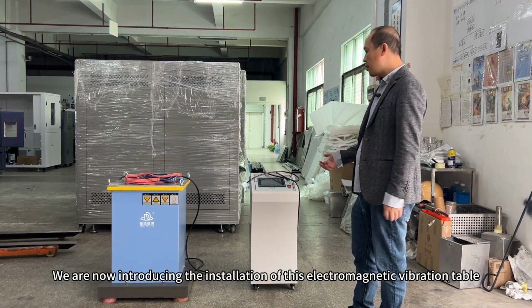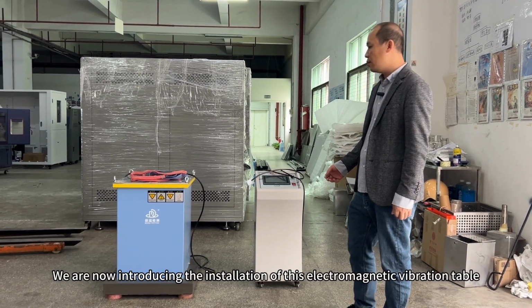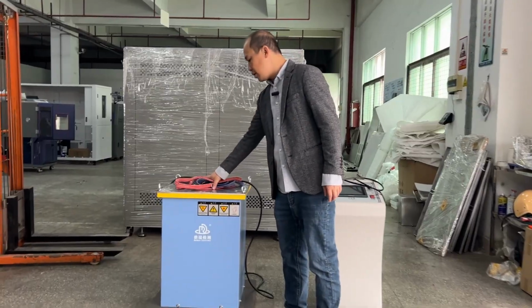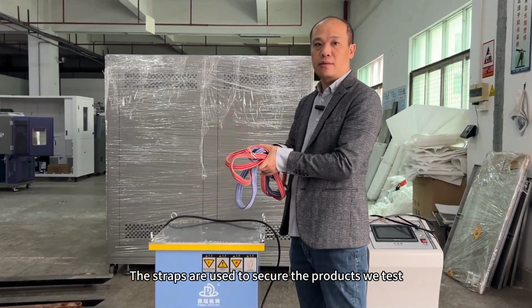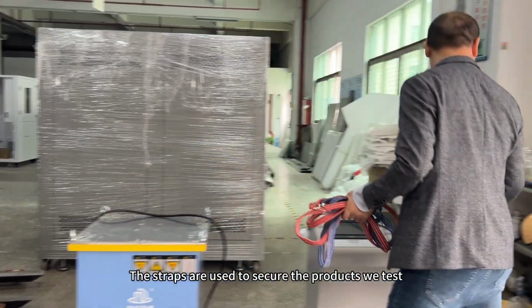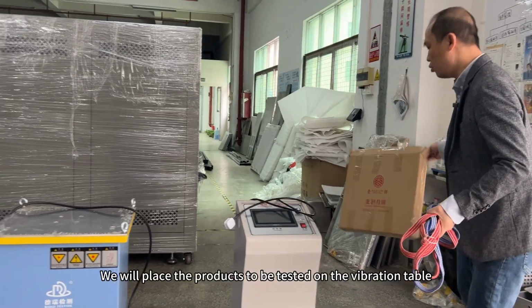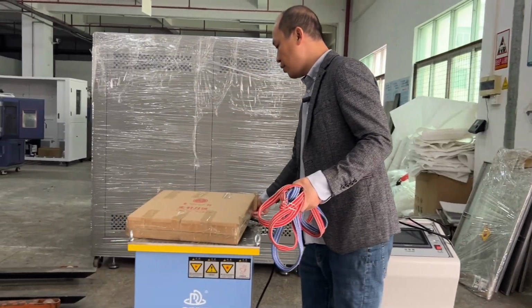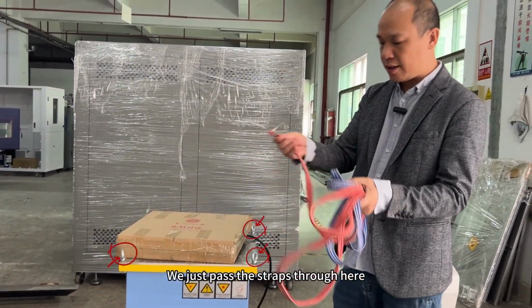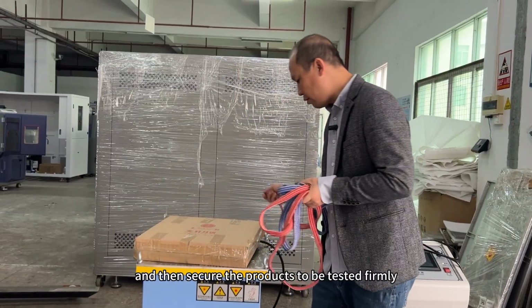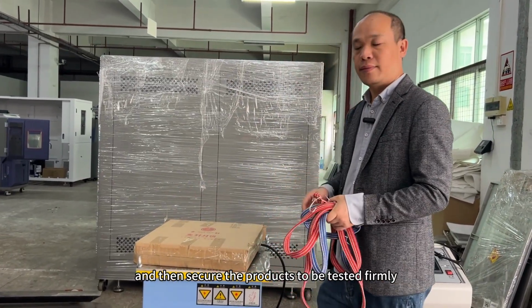We are now introducing the installation of this electromagnetic vibration table. These are our straps. The straps are used to secure the products we test. We will place the products to be tested on the vibration table. We just pass the straps through here, and then secure the products to be tested firmly.